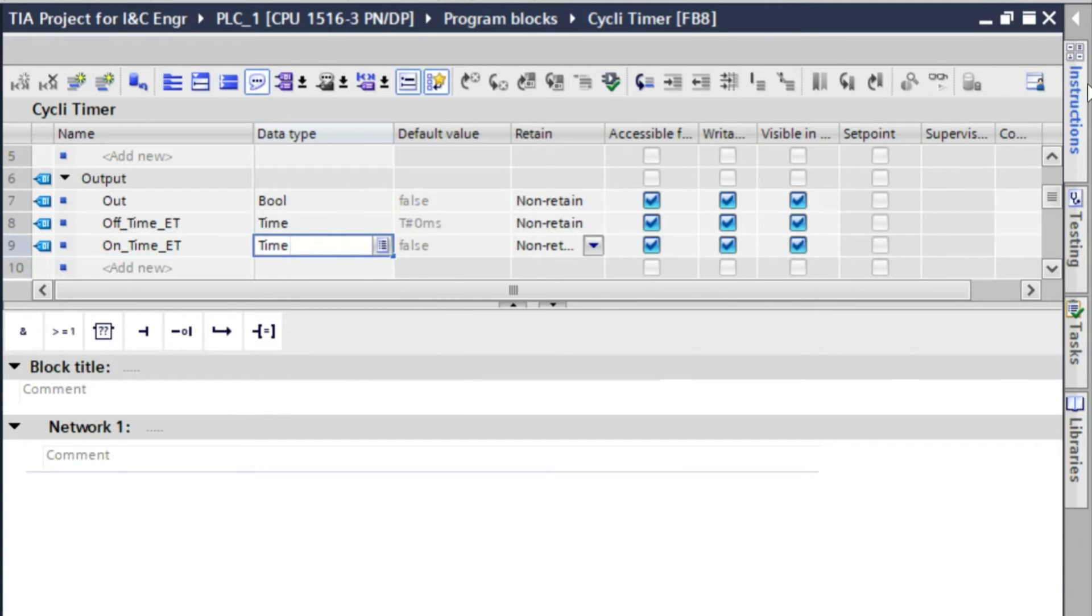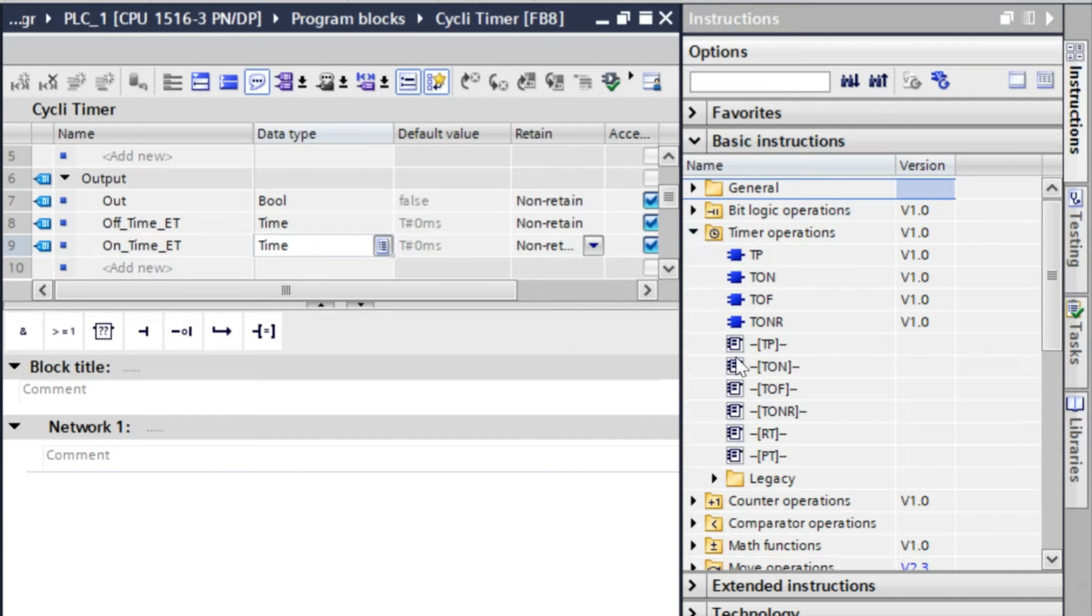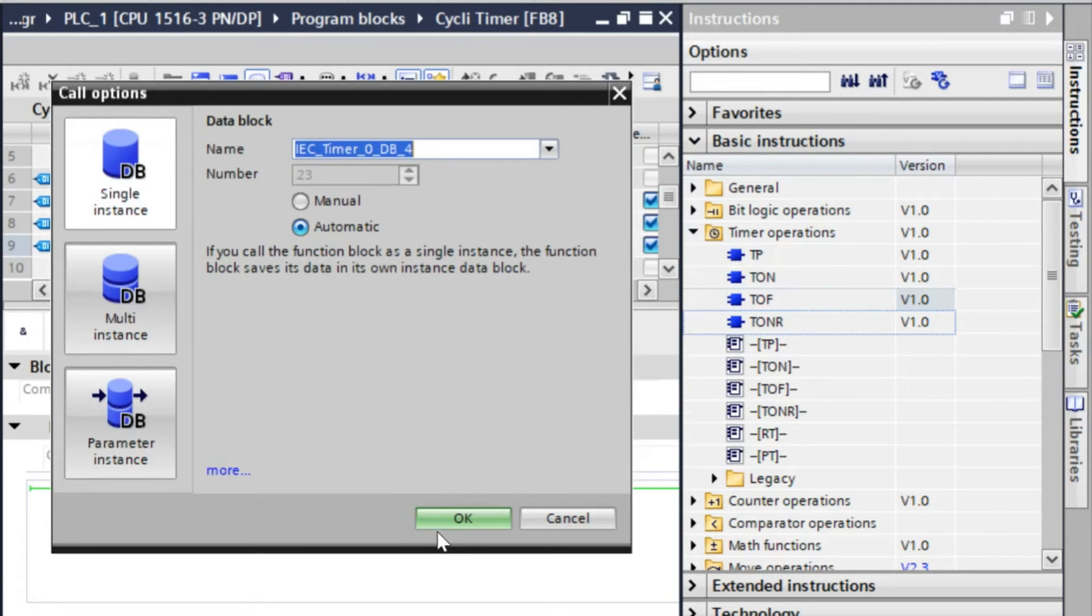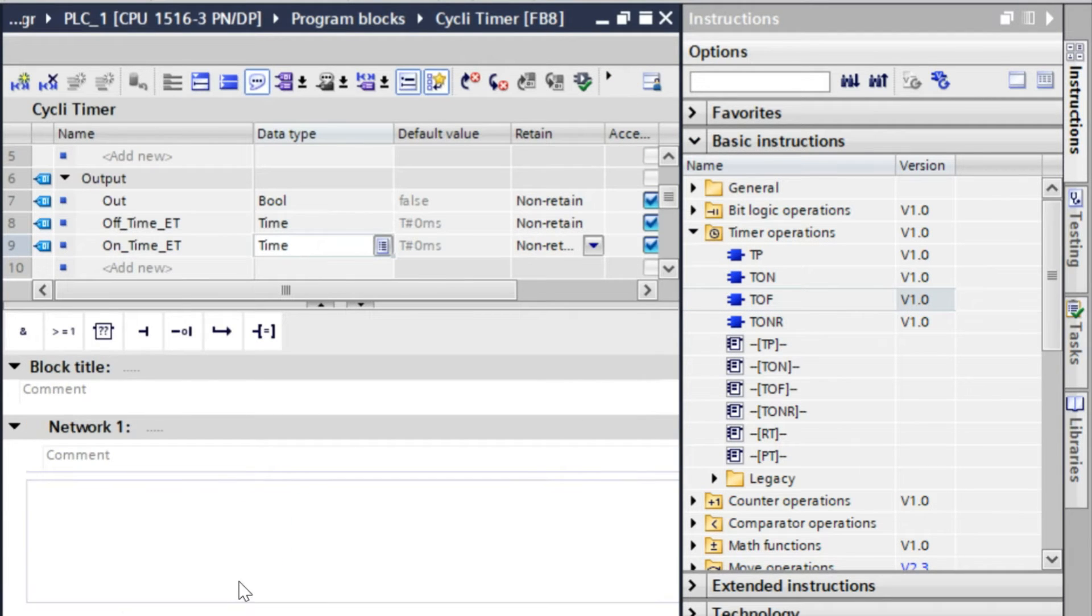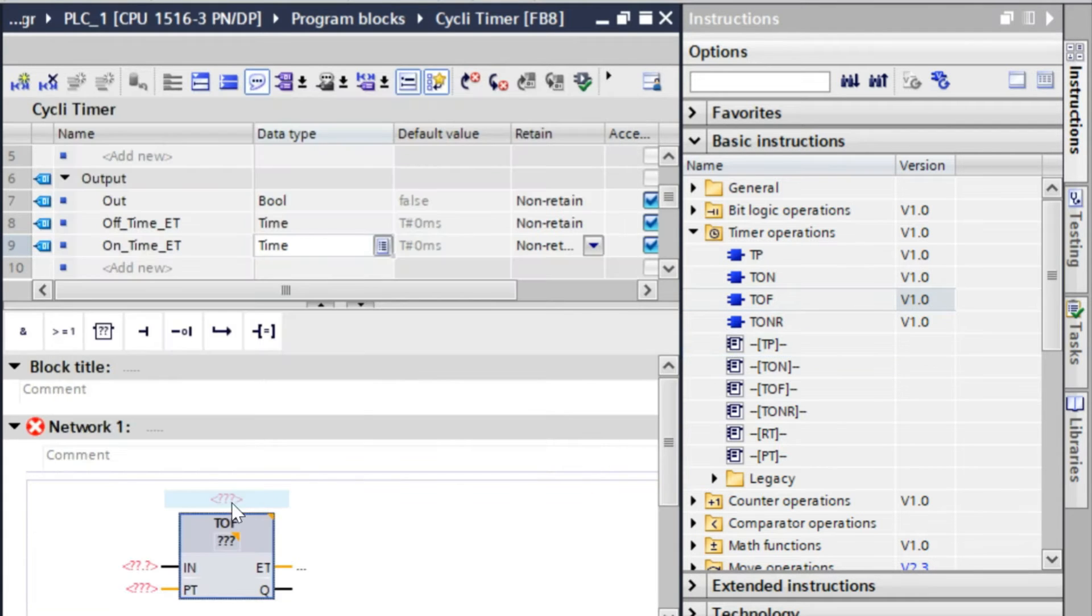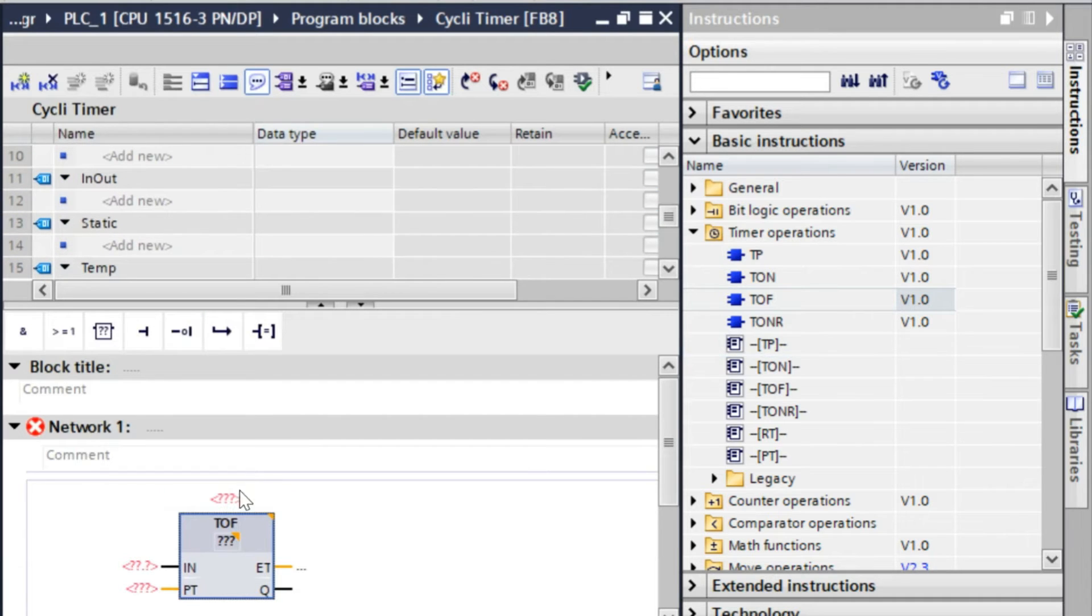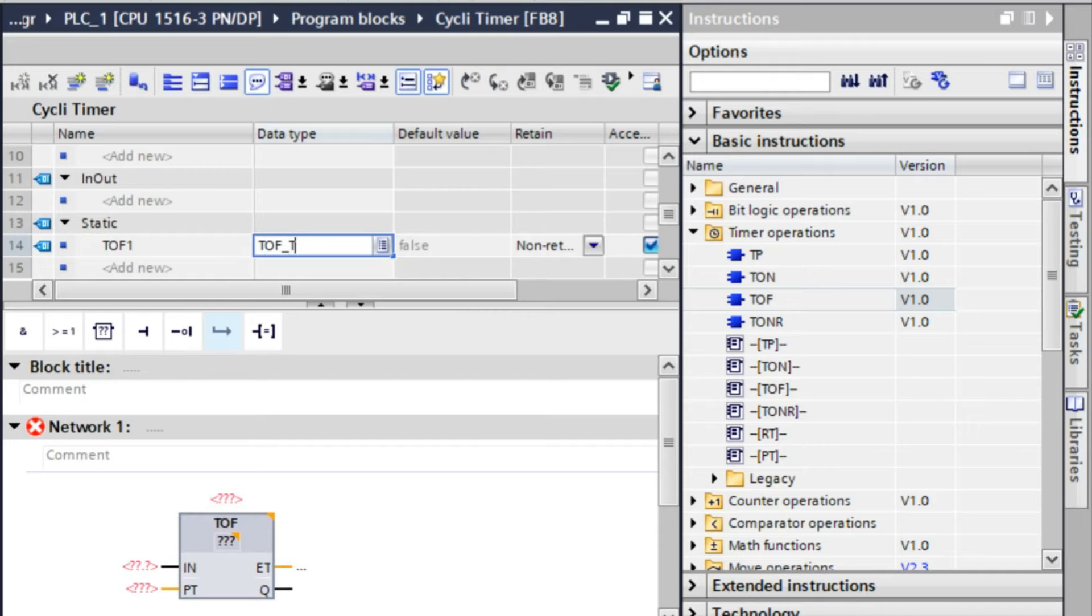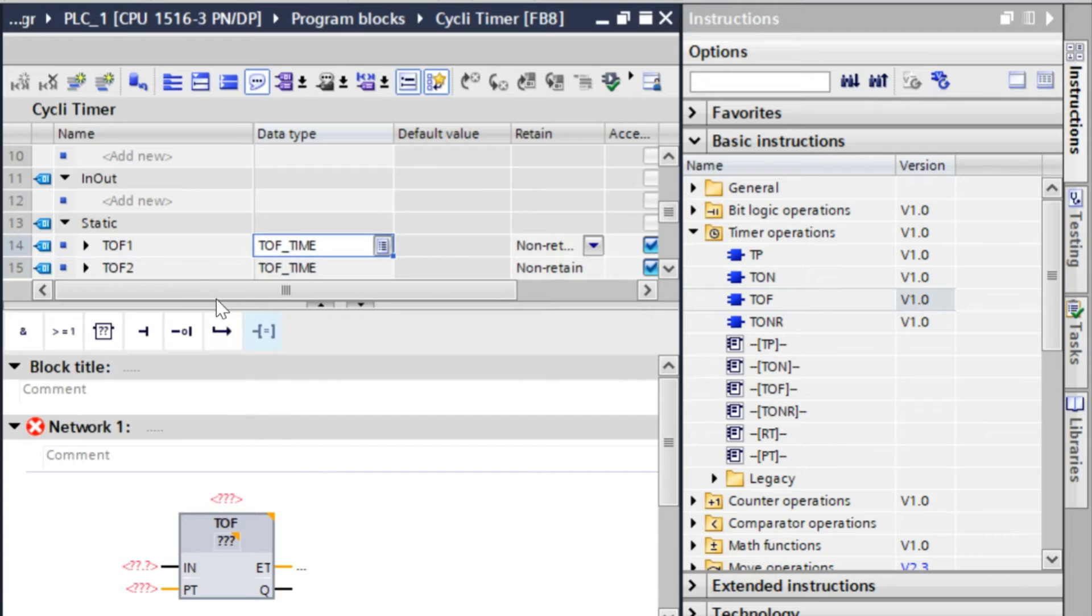Now we will take two timers, that's two TOF timers here. It will ask to create an instance data block instance DB. I will not create an instance DB, so I will cancel it. Here we have to put an instance data type that I will create here. It is an instance input section, so we will use a TOF timer. So we have to create a TOF time data type. And we will use two TOF timers, so there will be two instance DBs.